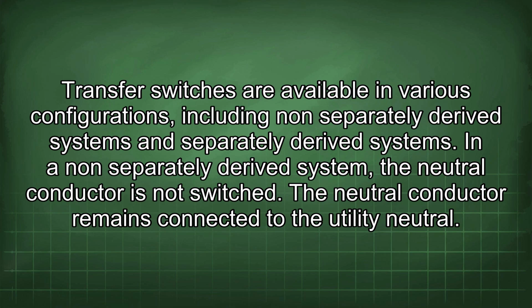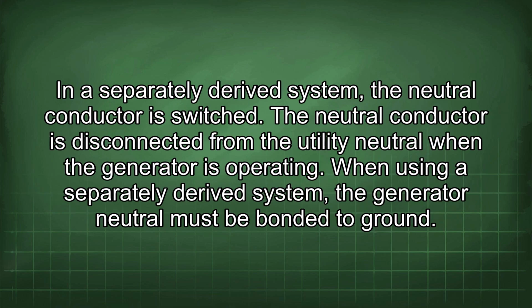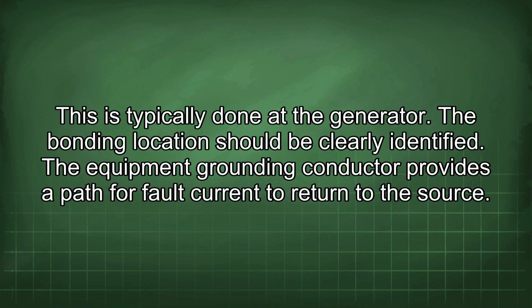In a non-separately derived system, the neutral conductor is not switched. The neutral conductor remains connected to the utility neutral. In a separately derived system, the neutral conductor is switched. The neutral conductor is disconnected from the utility neutral when the generator is operating. When using a separately derived system, the generator neutral must be bonded to ground. This is typically done at the generator. The bonding location should be clearly identified.